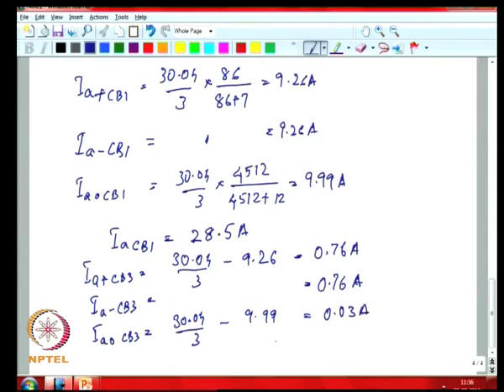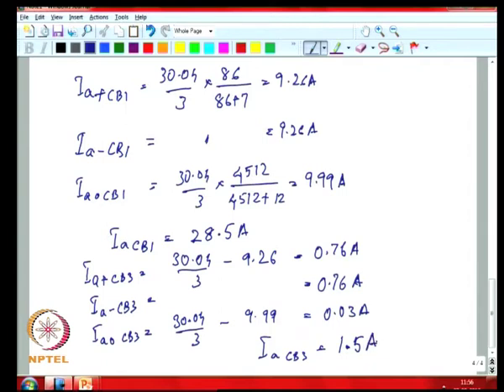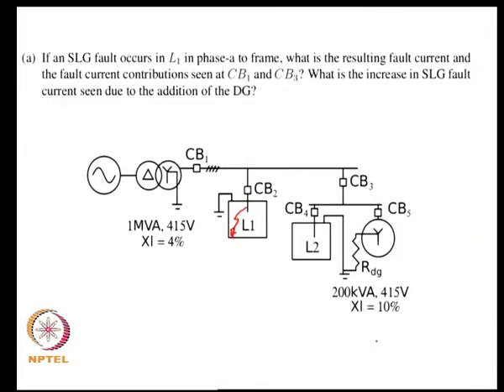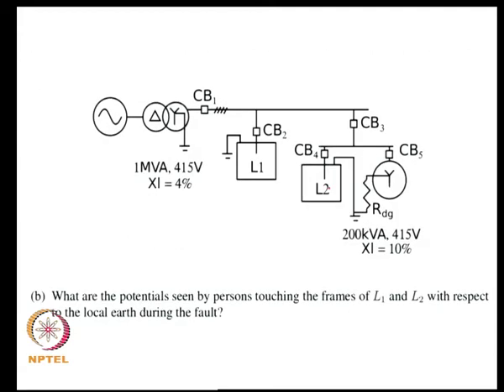If you then calculate what I_a through CB3 is—the sum of the three sequence currents—you have about 1.5 amps flowing through the circuit. At this point you have calculated the current flowing through CB1 and CB3 because of a fault in load L1. The next problem is to see what would be the touch potential for a person standing at load 1 or load 2.